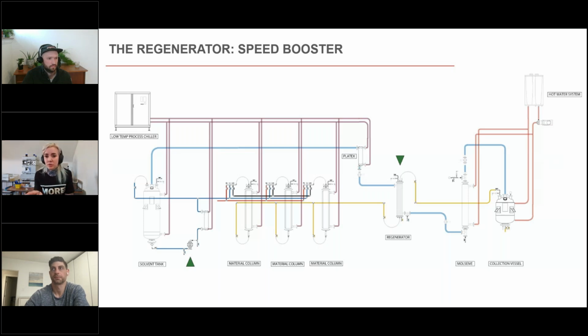That cleanability you were talking about with the tube and shell - a plate exchanger is just designed for that high volume throughput, so you're not going to have that kind of clogging that you get over time from a coil in the same way. And it's going to take up way less space in the facility compared to a series of big giant coils that require a lot of external insulation. A plate exchanger kind of insulates itself, which is really, really efficient.